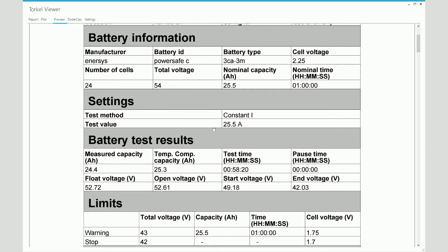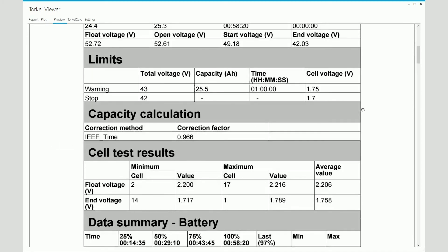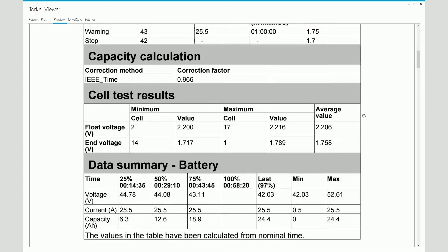Under settings, it shows you the test method that was selected and the test current value. Below that, it shows you a summary of the test results. You see the measured capacity, the temperature compensated capacity, the time, the test current, the voltage values recorded at the start, at the end, the float value, the open value. Under that, you see the limits that were set, the warning limits and the stop limits. Below that, you see the temperature correction factor that was used and the adjustment method that was selected.